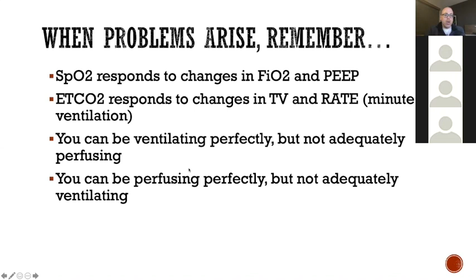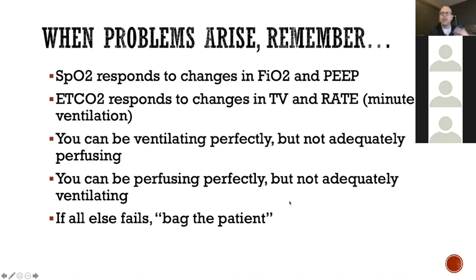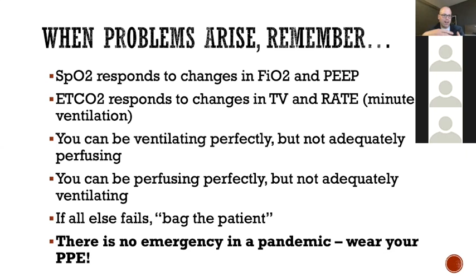Remember, you can be ventilating somebody perfectly, but not adequately perfusing them. You can be perfusing somebody perfectly, but not adequately ventilating them. If all else fails, you're getting alarms, you're not sure what's going on with it, take them off the vent, bag the patient, and then troubleshoot the ventilator. And remember, in a pandemic, there's not an emergency. So if something happens, you have a ventilator alarming, we're still going to wear our PPE before we go in and address that ventilator. They can go without the breath for a couple of breaths off the vent while we get our PPE on and get in there, okay?